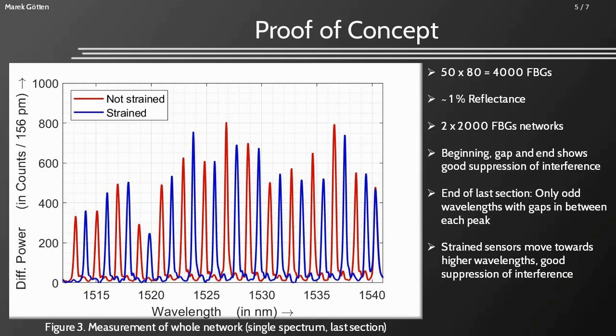When applying strain to sensor numbers 3987 to 4000, the peaks shift towards higher wavelengths. The most right sensor was not strained, so it stays at its current position. By shifting the peak wavelength, we see the interference of all other 49 sensors at these wavelengths, which is very low. The reflectance of all sensors is around 1%.